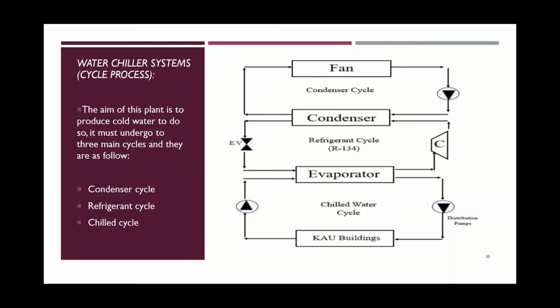The chilled water loop, which is the last cycle, consists of pipes and a distribution pump that move chilled water around the building. A chilled water pump pushes chilled water through the chiller and through the chilled water line around the building, and the water returns into the evaporator at 11.3 degrees Celsius. The chilled water that exits the chiller is called the chilled water supply.